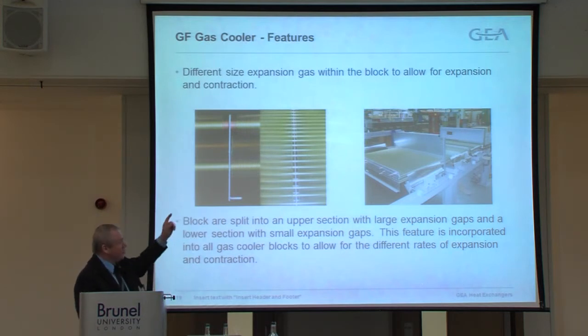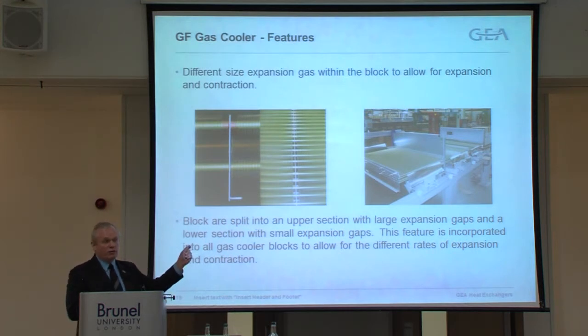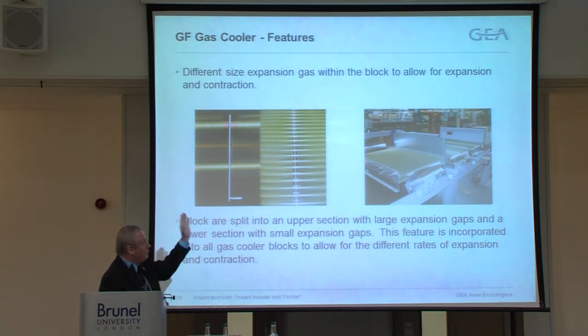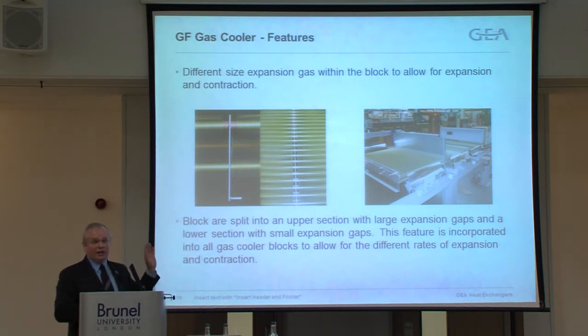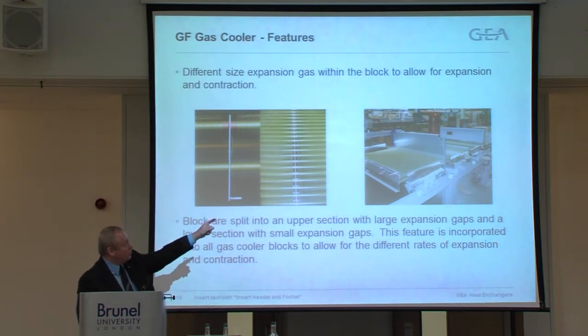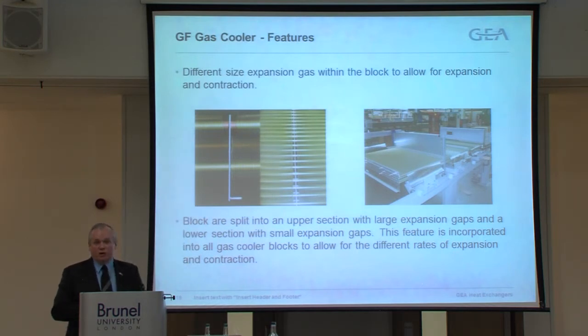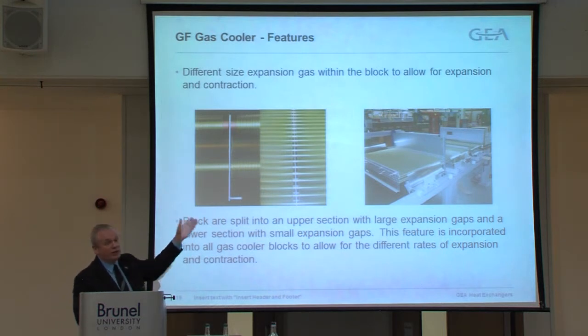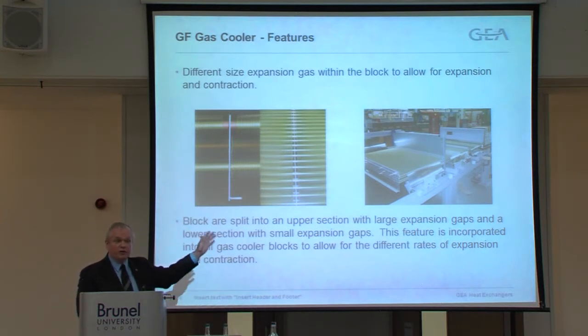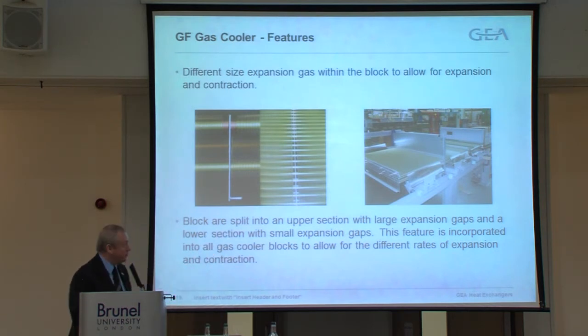And indeed, what we actually do is that we put expansion gaps in the matrix as well. Larger on the top section, smaller on the bottom section, and then we support the coil in between with an aluminium tube sheet. You can see on the far photograph, you've got a unit that's being partly built, and the two plates that are sticking up at the top are actually fan baffles. So they actually stop the recirculation, but now they go entirely through the matrix. So you're supporting the coil on every single module that you've actually got.